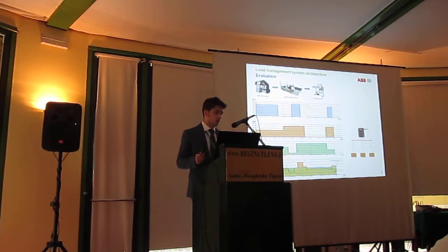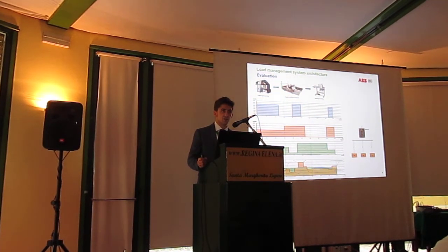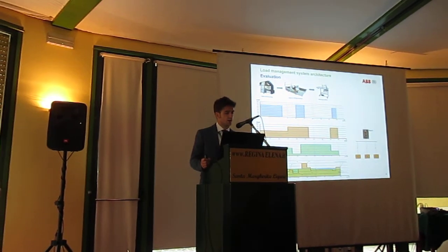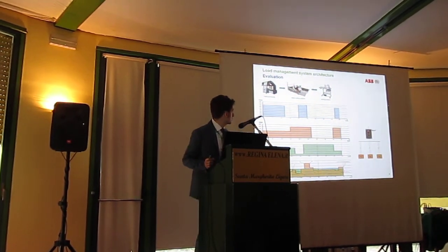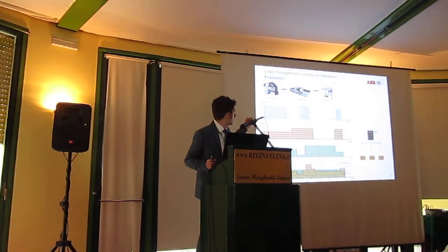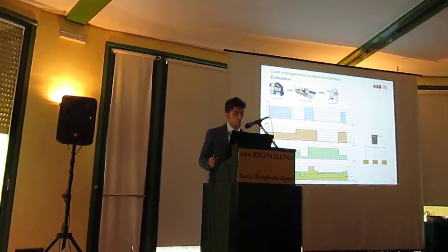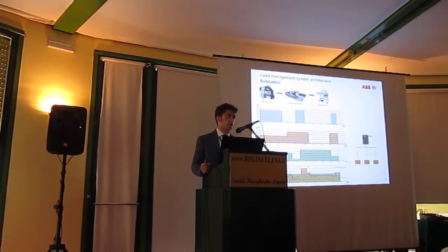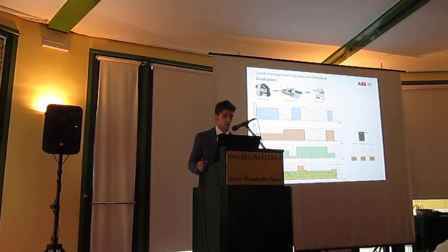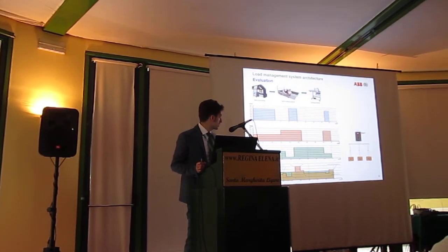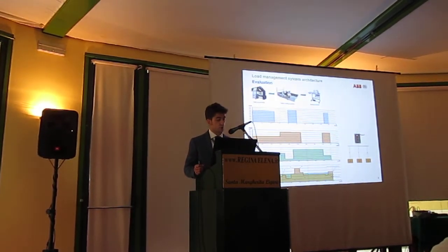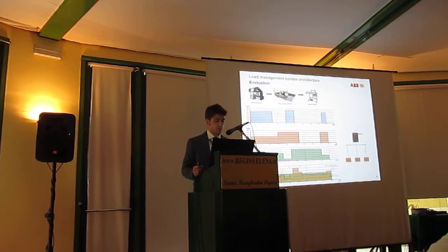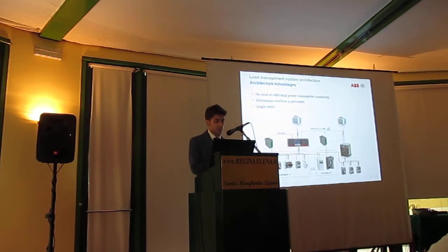Okay, here the described features are depicted in a simple example, a textile factory, where you will see that there are a couple of loads with different priorities from left to right. The priorities are decreasing, so the one on the right can be disconnected more frequently than the others. None of the loads have been connected or disconnected together simultaneously, and the total final average power is within the acceptable range.